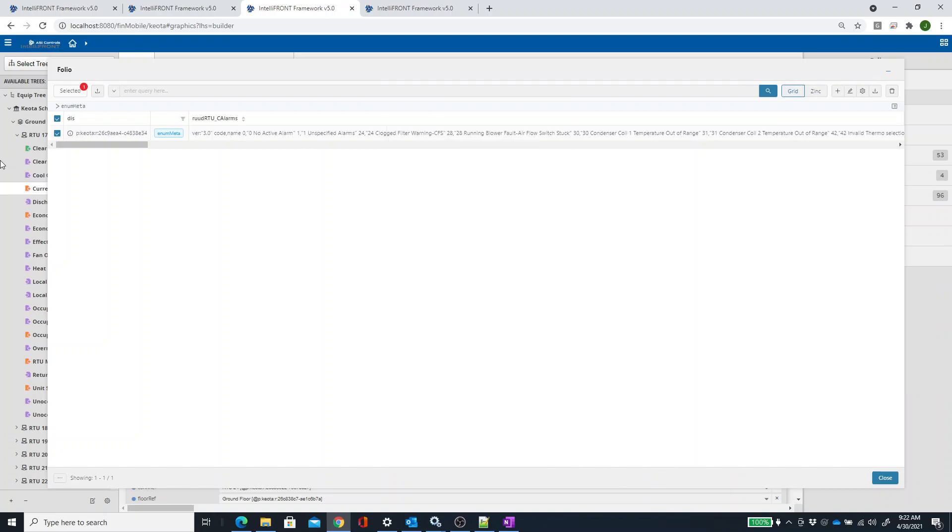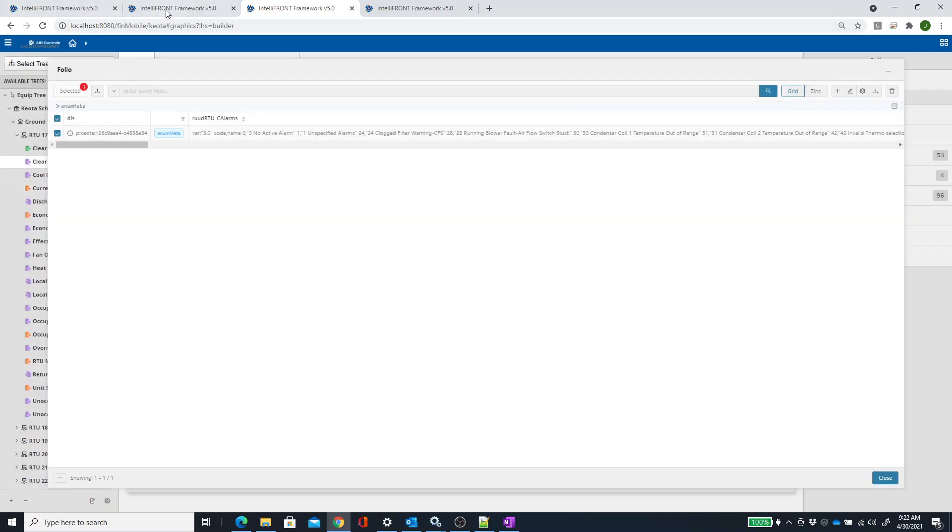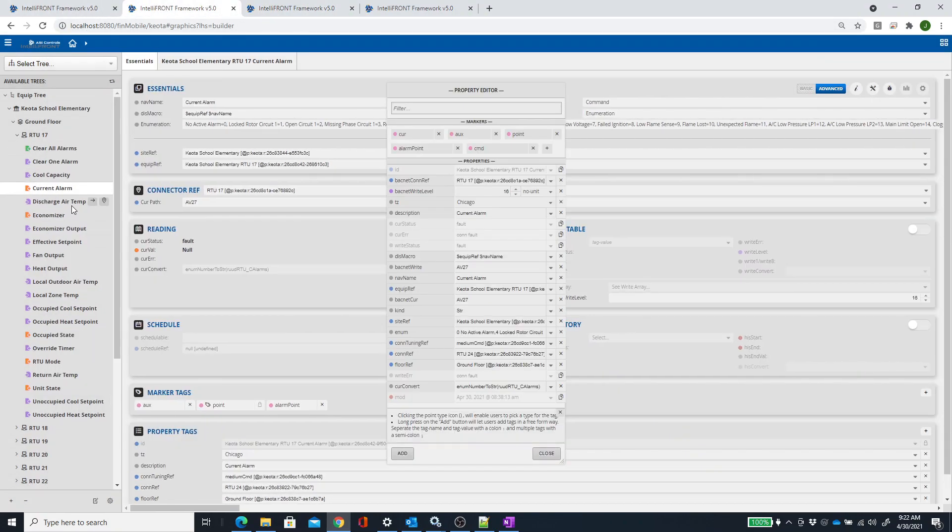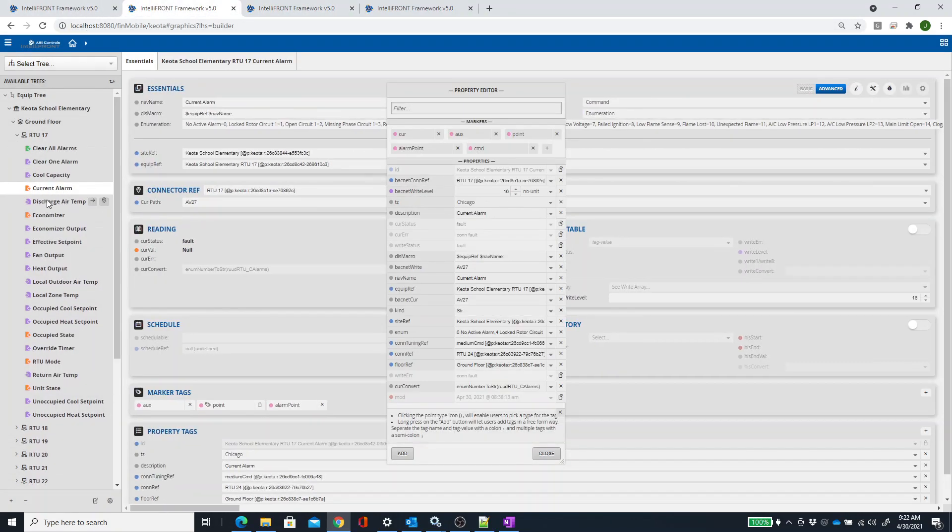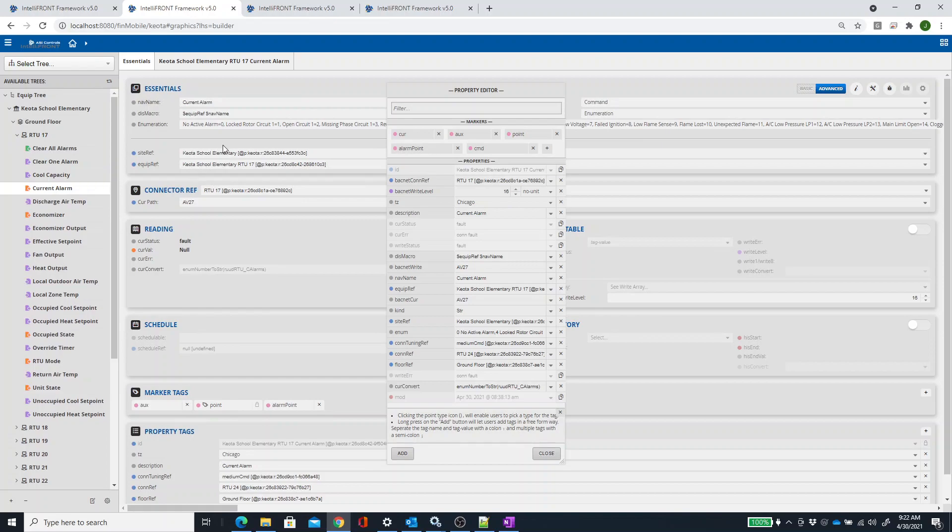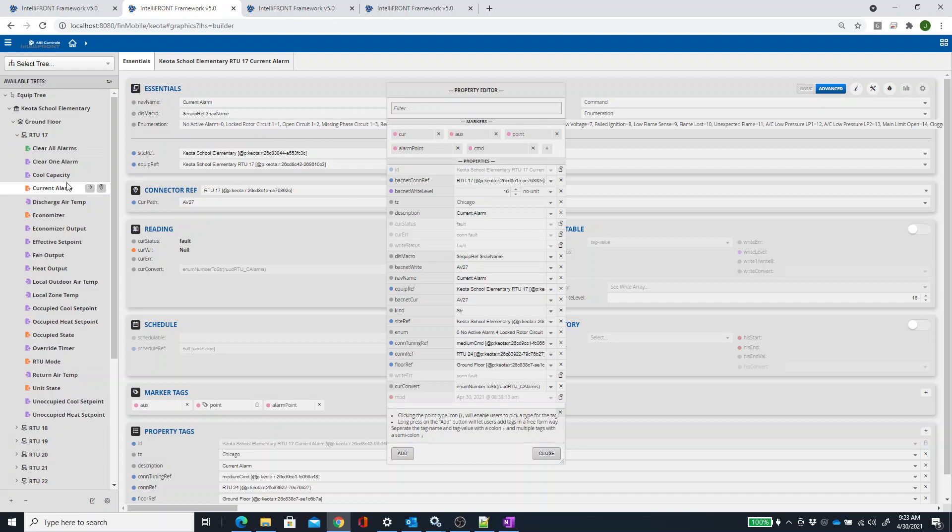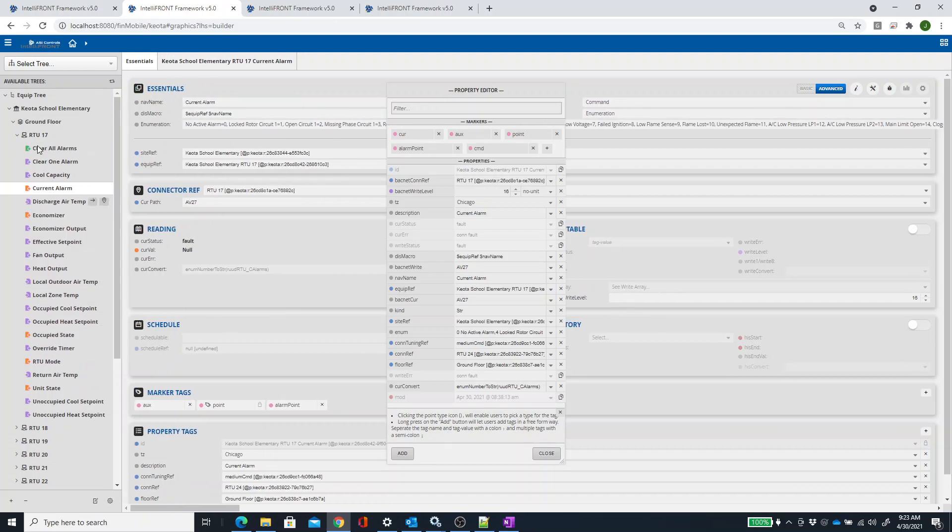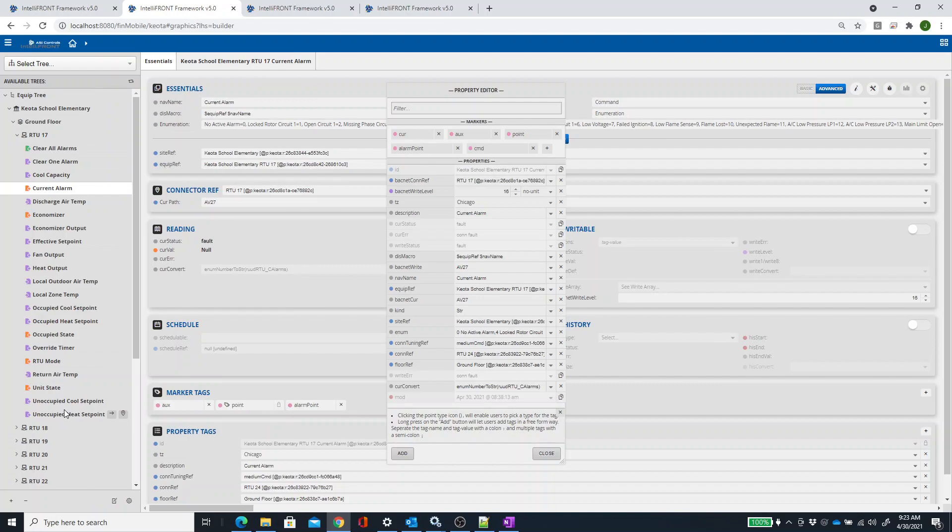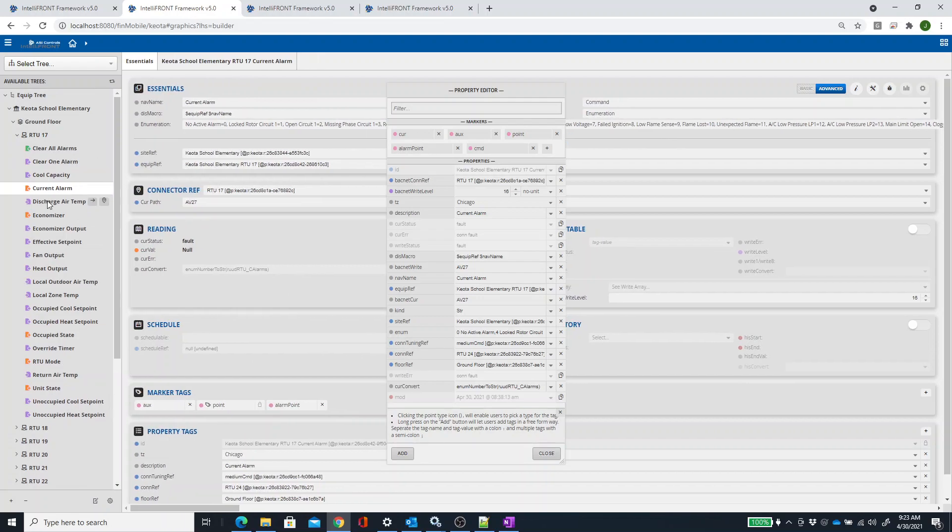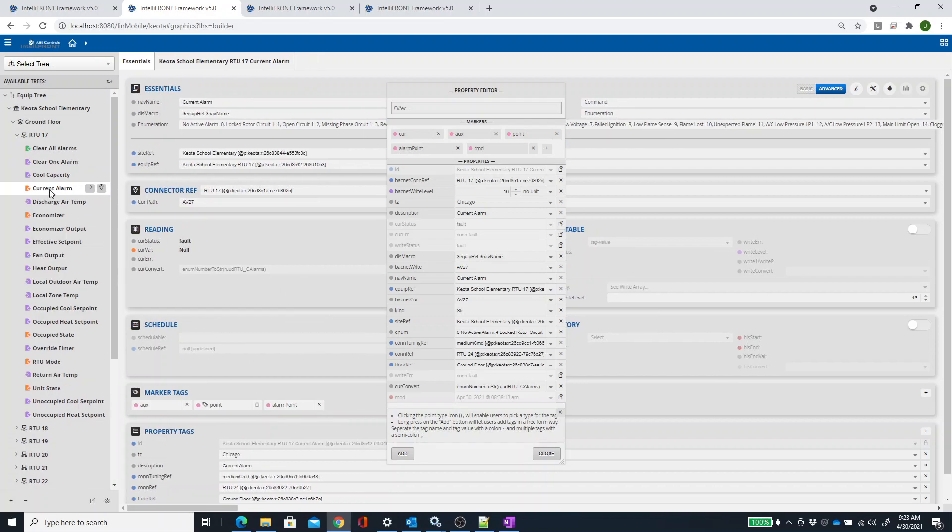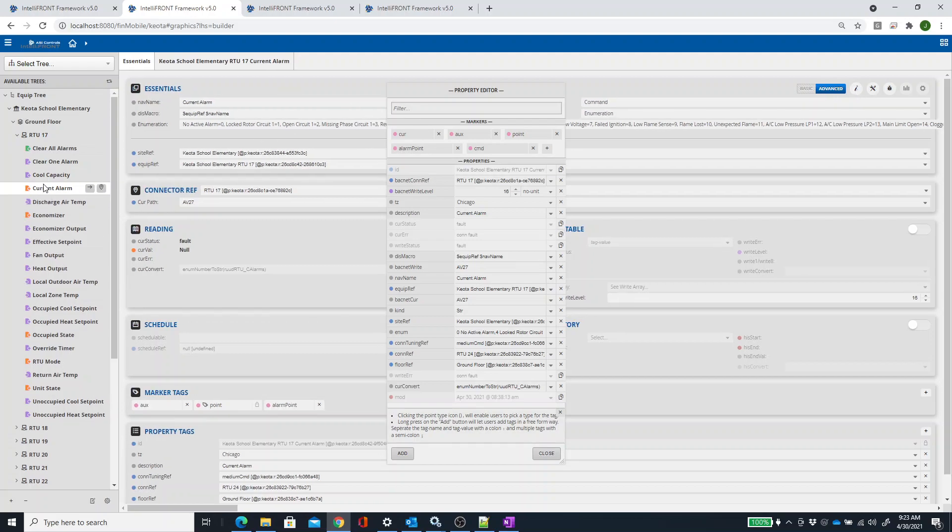Now, you're not done, because if you go back to dbbuilder, you can see that this current alarm, there's this enumeration string up here. So that enumeration string will not update unless you reapply that list. Well, I have eight rooftops. If I was only going to do, if I only had one point underneath one RTU, say it was a unique RTU, then you would just go to your i button up here underneath that current alarm.